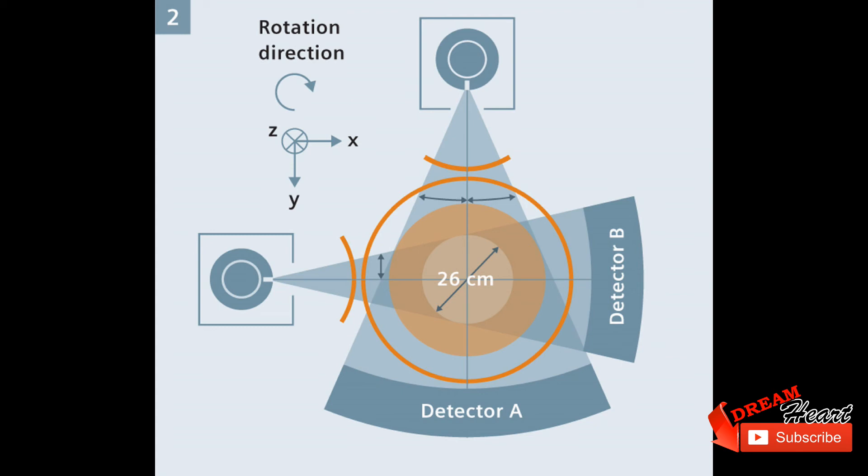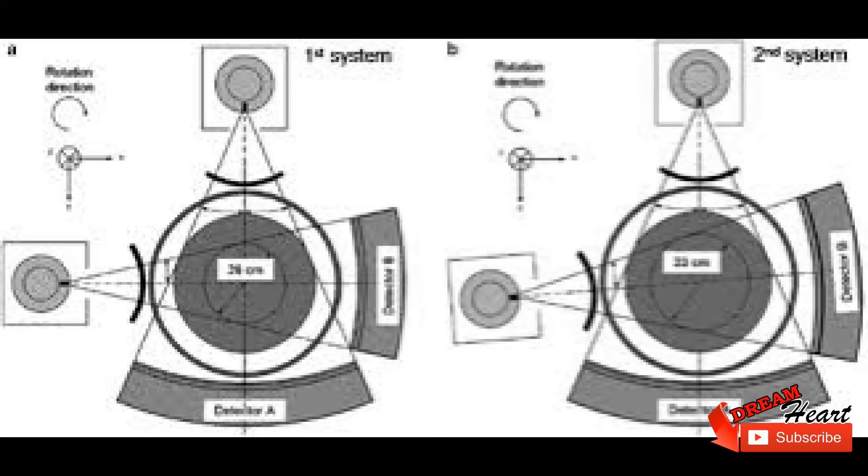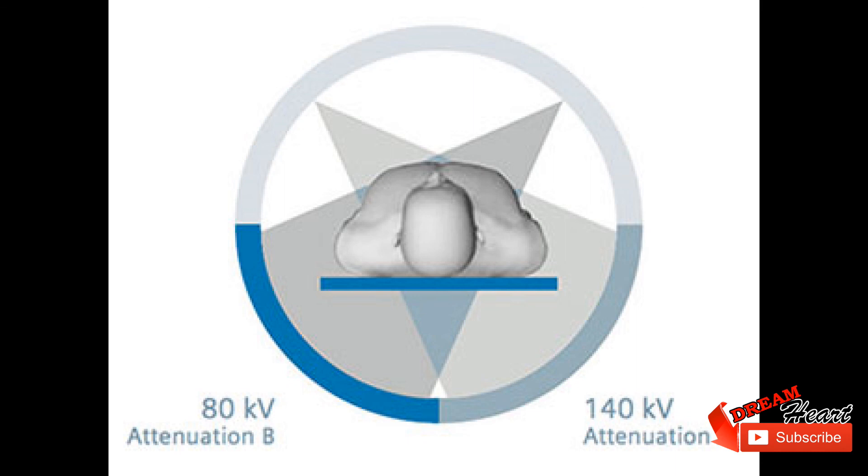Siemens introduced a CT model with dual x-ray tube and dual array of 64 slice detectors at the 2005 Radiological Society of North America RSNA medical meeting. Dual sources increase the temporal resolution by reducing the rotation angle required to acquire a complete image.